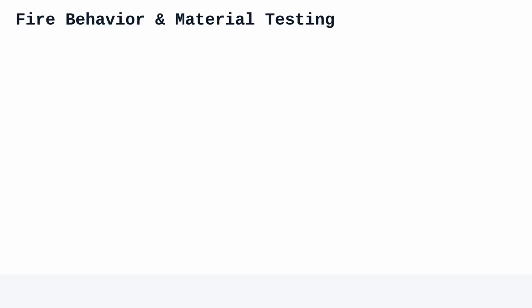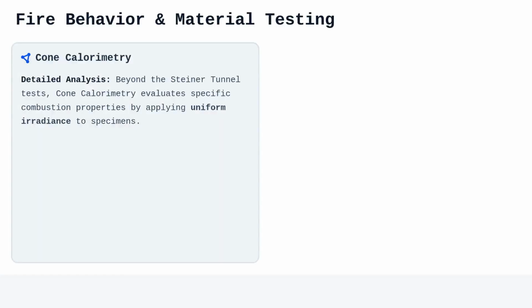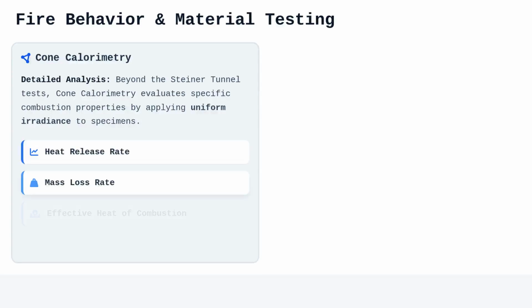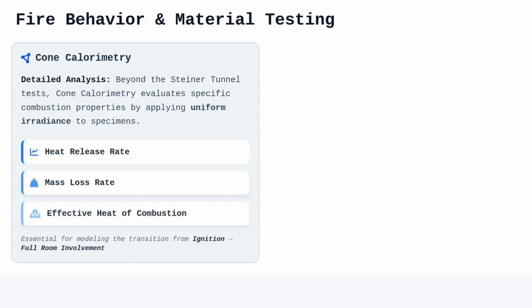Beyond the Steiner tunnel, we utilize cone calorimetry to delve deeper into the material's specific combustion properties. This test exposes a small specimen to a uniform irradiance, allowing us to calculate the heat release rate, mass loss rate, and effective heat of combustion. These parameters are essential when modeling fire spread, as they account for the transition between ignition and full room involvement.